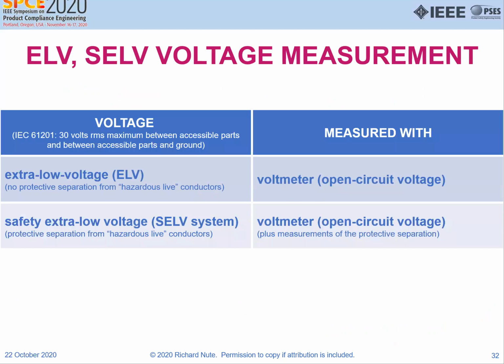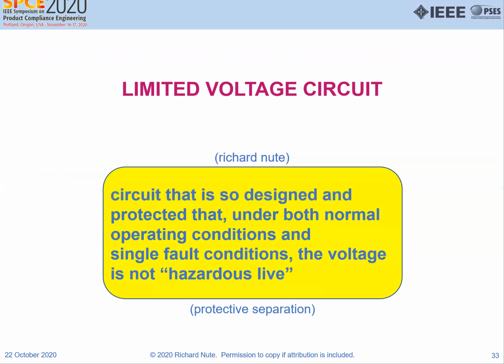And we'll do the measurements. The ELV is measured with a voltmeter. The safety extra low voltage is also measured with a voltmeter, plus the measurements of the protective separation. So a limited voltage circuit is a circuit that is so designed and protected that under both normal operating conditions and single fault conditions, the voltage is not hazardous live. All right.